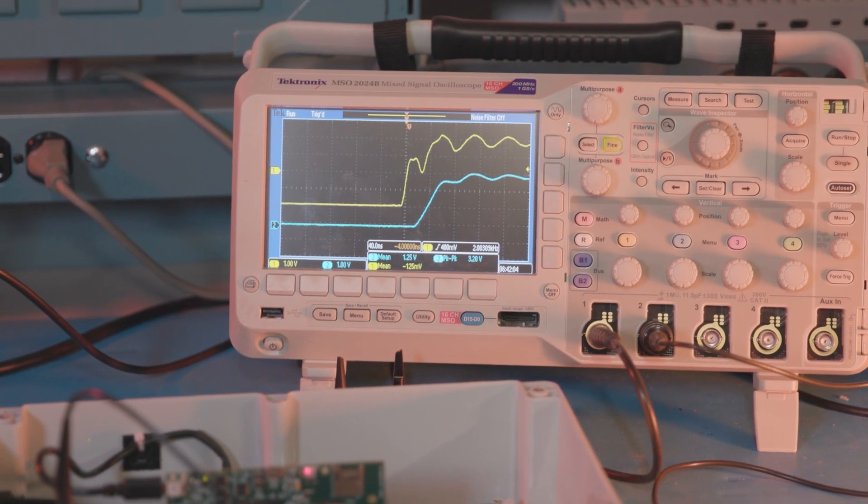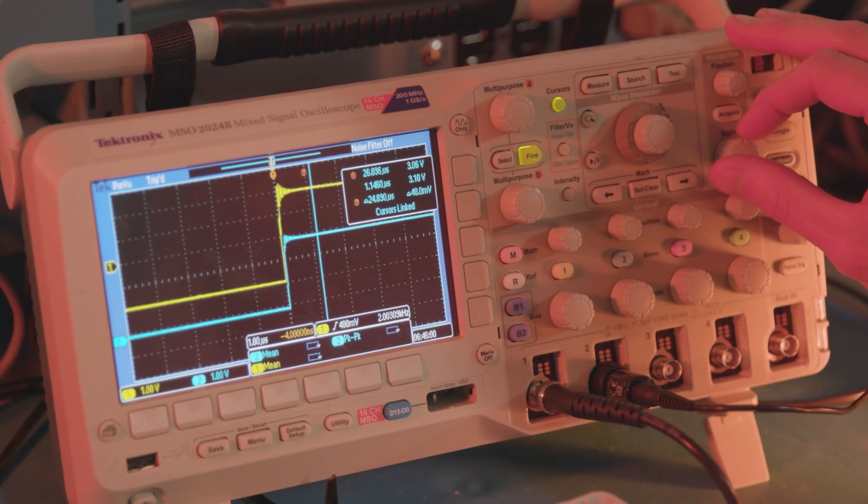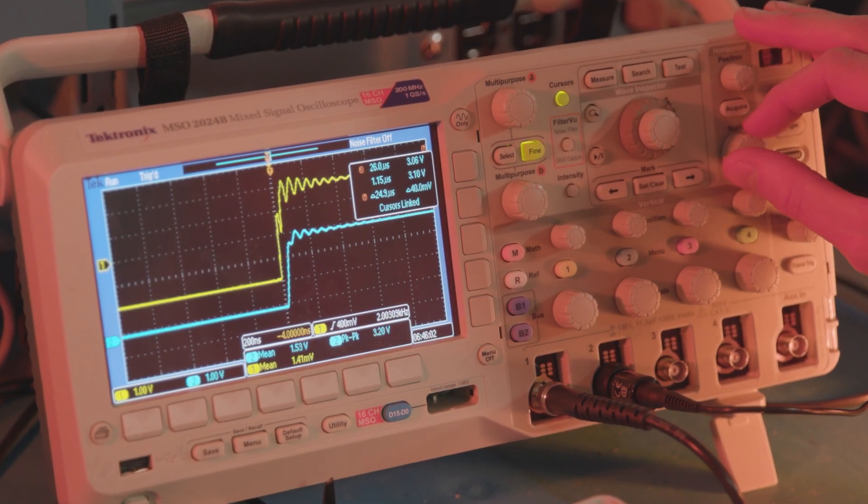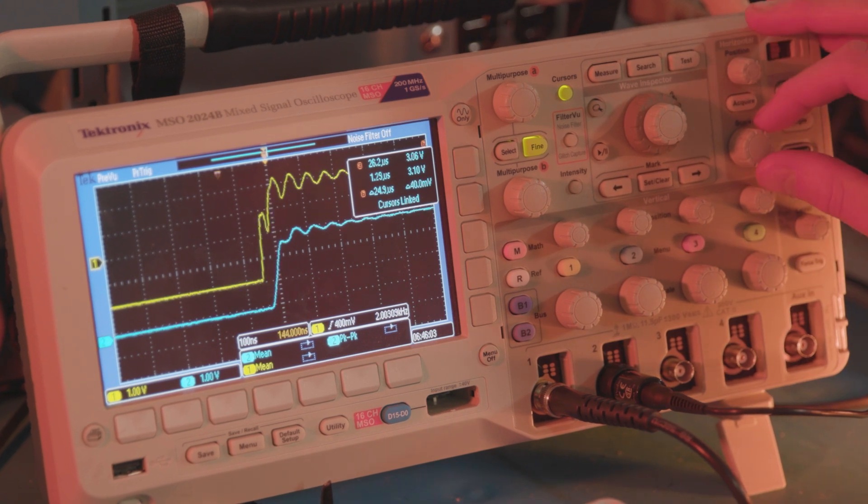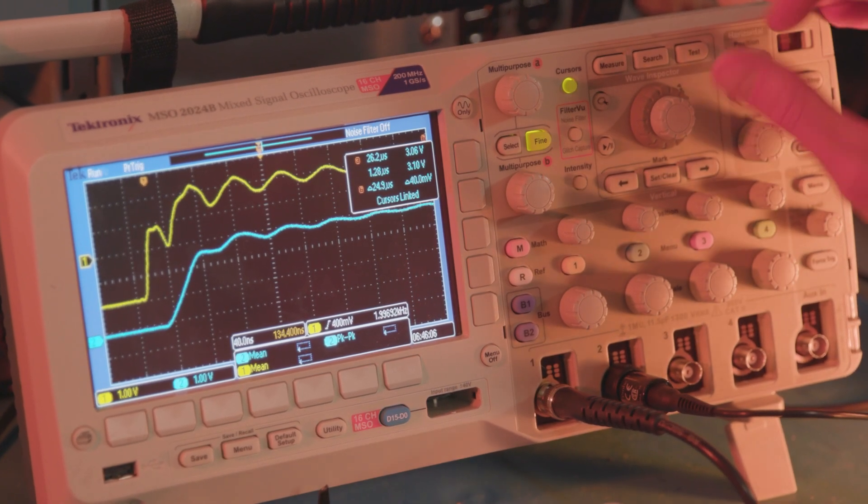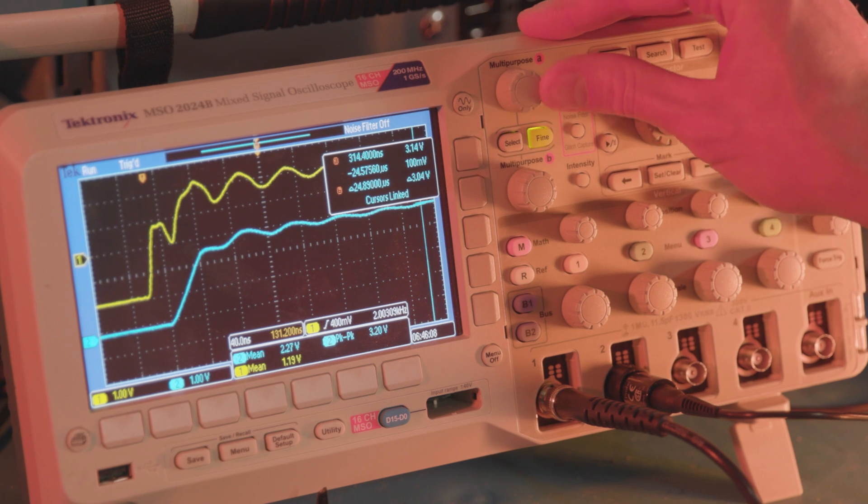The hardware is designed to capture only the traveling wave fault's high-frequency content. There is analog filtering of the sensed waveforms to block any higher-frequency electromagnetic and radio frequency interference, reducing false detection and signal errors caused by these external noise sources.